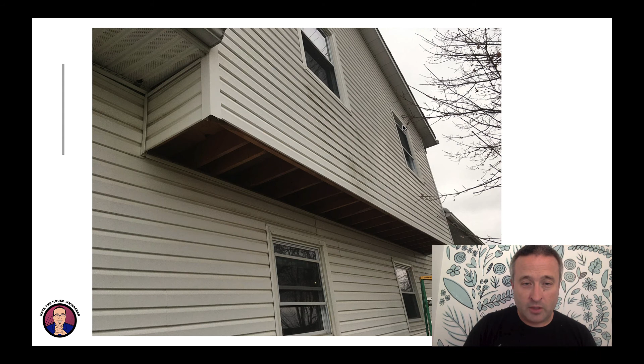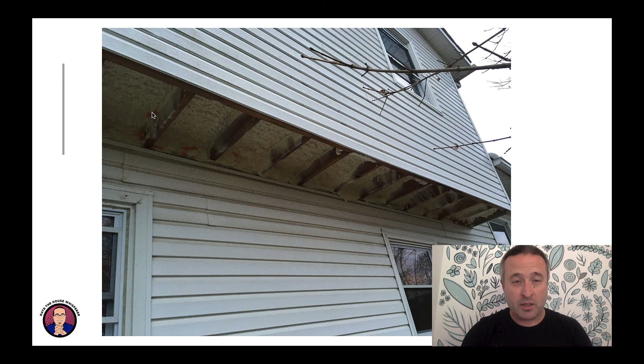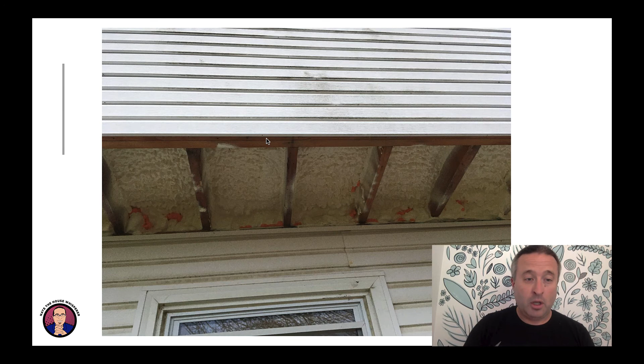So there it is, all opened up, and here it is getting sprayed. Note here the little bit of orange, that's me doing QC. I don't know for sure if it leaked because I wasn't checking with the blower door, but if it looked like it leaked, I had a little can of foam that I was touching up with. Quality control will make or break these projects. It's really critical.